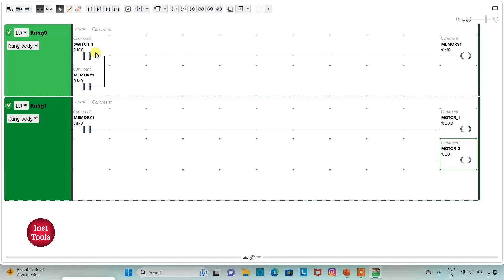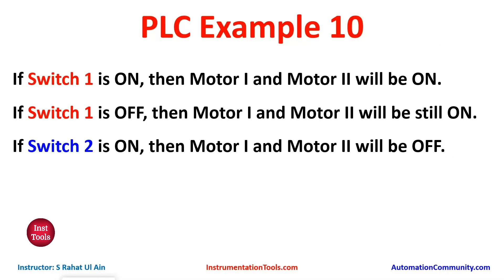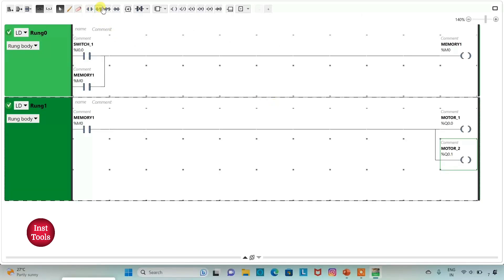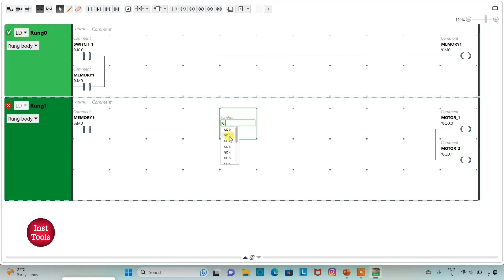So when SWITCH1 will be on, MEMORY1 will be TRUE, and when MEMORY1 is TRUE, MOTOR1 and MOTOR2 will be on. If we turn off SWITCH1, MEMORY1 will remain TRUE and MOTOR1 and MOTOR2 will still remain on. To turn them off when SWITCH2 is on, we will take SWITCH2 as a normally closed contact. I will insert a normally closed contact and assign address I0.1 with symbol SWITCH2.